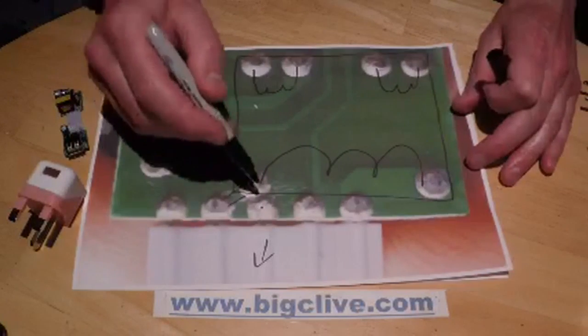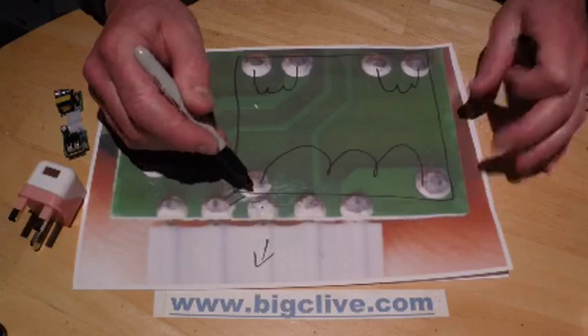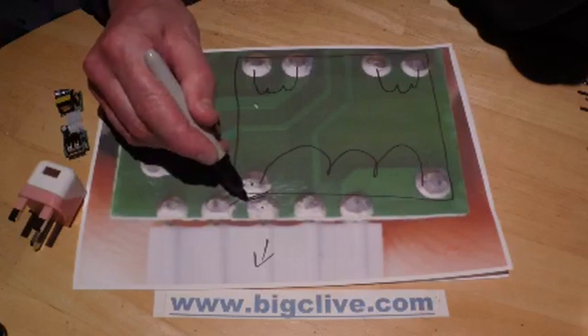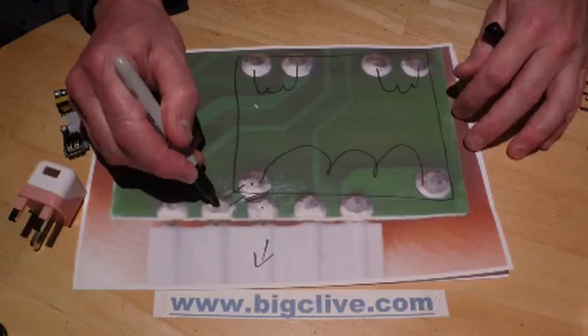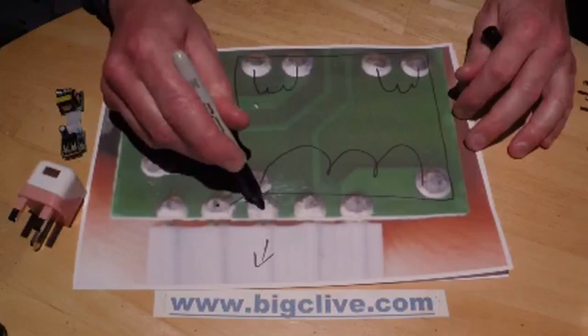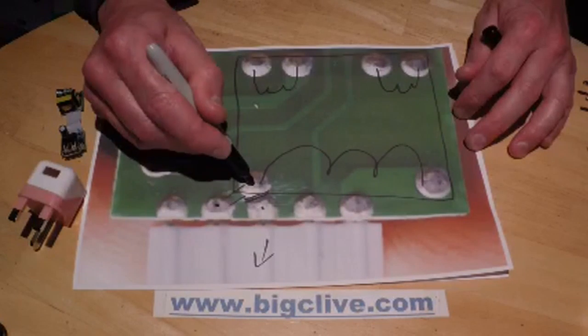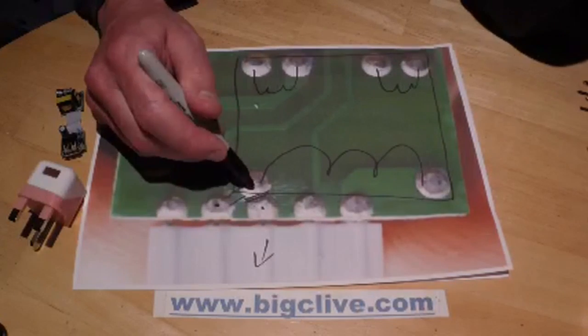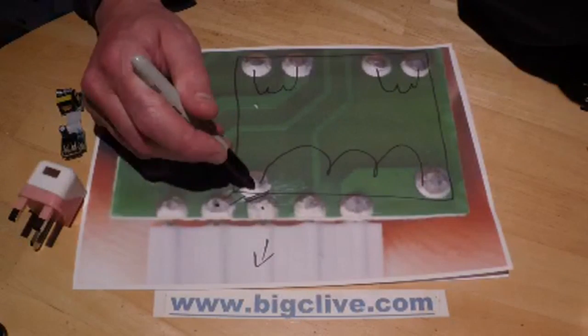Although they look it, and I had to look at this through a microscope to see what distance there was of separation, because it turns out that this is a low voltage connection, and this is a high voltage connection. And this low voltage connection is connected by a track to this one. So these two pads are basically the only isolation between the high voltage and low voltage side.